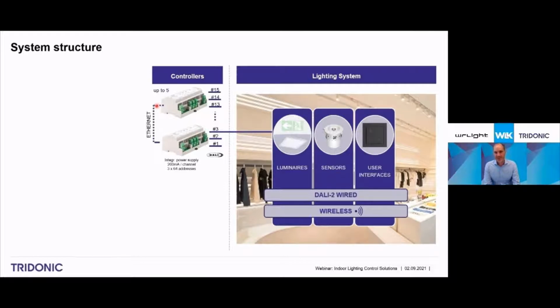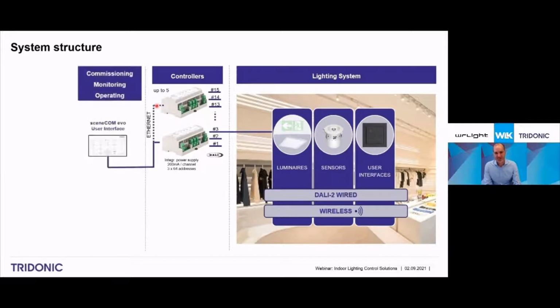And that really gives you the possibility to have at the moment a maximum of 15 DALI lines available in your building, which is roughly around 1,000 luminaires to connect, and sensors on top of that through the DALI 2 implementation that we have available.